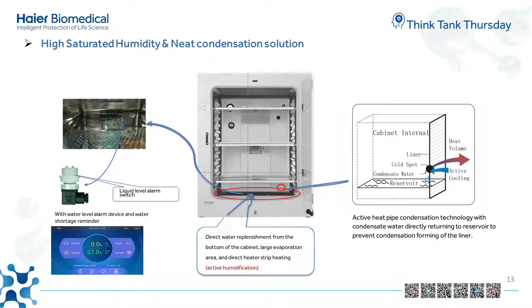With all these designs to reach optimal cell growth requirements, a fast recovery after the door opening can be easily achieved as well. Adopting an active airflow control technology based on the fuzzy PID control principle, the parameters can be restored without overshoot. The temperature and the CO2 concentration can be quickly restored within 4 minutes. When the door is open, the high precision fan stops rotating to avoid the influence caused by convection. But when the door is closed, the fan speed is intelligently controlled and all parameters are restored quickly.